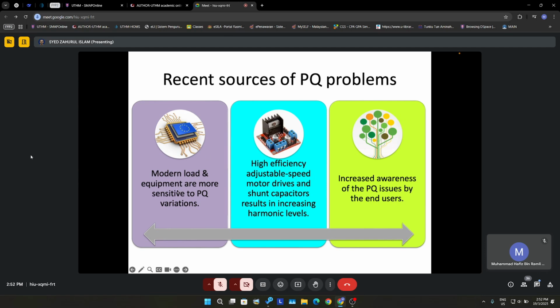So the modern loads and equipment are more sensitive to PQ variation - high efficiency adjustable speed motor drives, and shunt capacitors result in increased harmonics levels. So we have the sensitive equipment on one hand, and on the other hand we have high efficiency adjustable speed motor drivers and shunt capacitors we use. We'll look at shunt capacitors later - that's actually the cause of the harmonics level.